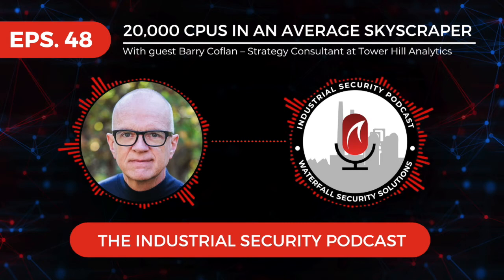You mentioned two protocols, BACnet and IoT. Is that IoT Internet of Things, or IoT something else, or did I get it wrong? Yeah, IoT is more of an architectural construct of Internet of Things, where you've got these smart sensors and smart devices that you put into a building. They're not necessarily connected on the VLAN to the BMS directly. It's going out over the cloud itself. It has its own cloud connection as a device, and then the data goes up to the cloud and is relayed back down into the BMS.